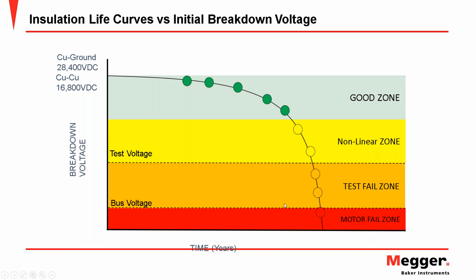But imagine if design engineers didn't start us off at this higher value. What if it was just a 2,000 volt insulation to ground for our 460 volt motor? Well, the room to degrade is far less, and of course, once the switching surges, which are at test voltage, or in some cases are even above the test voltage, those are going to cause internal arcs, which are going to accelerate that insulation degradation probably even faster. So it's more likely that our curves would be really small. These motors would last for very short intervals. And of course, you'd probably take that manufacturer and tell them you no longer want their products. So you can see why it's important that they design them this way.